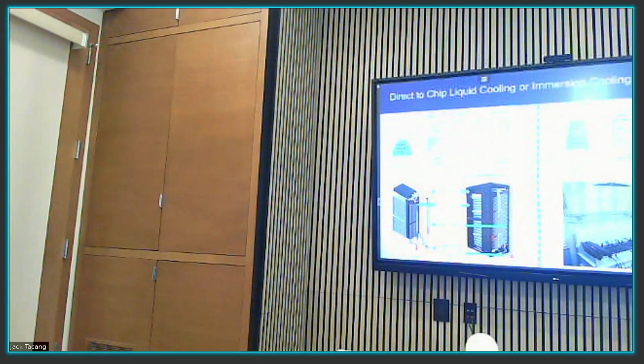So effectively, there are two different types of liquid cooling solutions out there. I say that generally speaking, because in reality there's much more than this, but if I were to generalize, we're basically looking at direct-to-chip liquid cooling or immersion cooling. The difference with direct-to-chip is that we have a device known as a CDU, or coolant distribution unit, that pumps liquid, typically water, because water is probably the most efficient liquid we have for cooling. It pumps that liquid directly into the server through tubing. On top of the chipset we have what's called a cold plate, so the tubing goes right through the cold plate, and as the liquid moves through it, it extracts the heat directly from the chip, right? Then that loop goes back to a heat exchanger, which takes the heat out of the system, and the liquid returns and repeats the cycle.